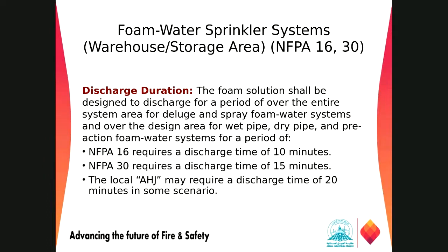NFPA 16 requires 10 minutes, NFPA 30 requires 15 minutes. And sometimes the local AHJ, the civil defense team, or the SCIS, or maybe the loss prevention department, have their own requirement up to 20 minutes, right? So this is our duration.